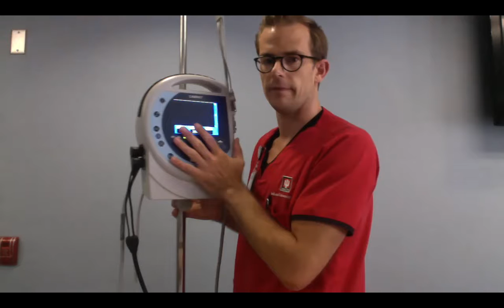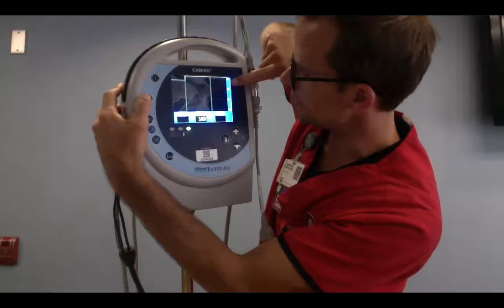A few things to note on the Camino monitor. It's going to give you an ICP here, a numerical value. It will give you a graph, and you can press this button to adjust the graph. So here we see 0 to 100. Now it's 0 to 200. Now it's -5 to 10. Now it's -10 to 20. Now it's 0 to 50.